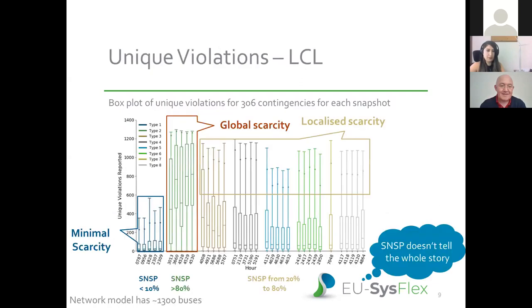So a couple of box plots here. We ran about 300 contingencies for each snapshot, and we studied a selection of points from across that gray space I showed. On the left, you have the blue and the green, which are again type 1 and type 2, so your low penetration and your high penetration. And you can see that in terms of unique violations, at low penetration, there's really no problem. But at high penetration, there's a big problem. About 3/4 of the system, in this case, will see less than 0.5 per unit when the fault comes on, which means any fault is propagating really far and wide across the system, which isn't something that we see today.